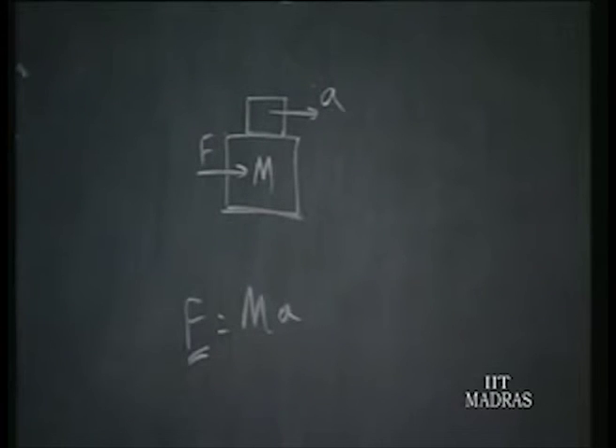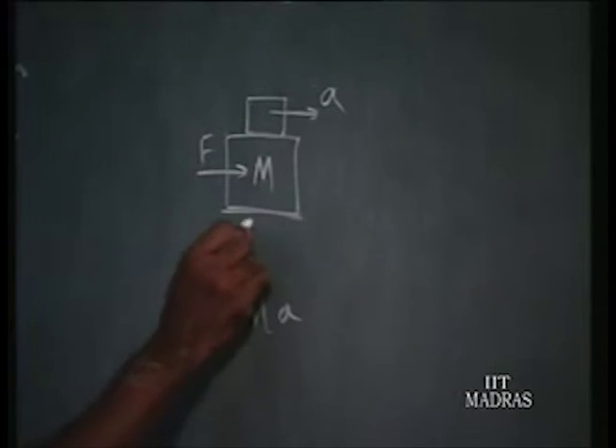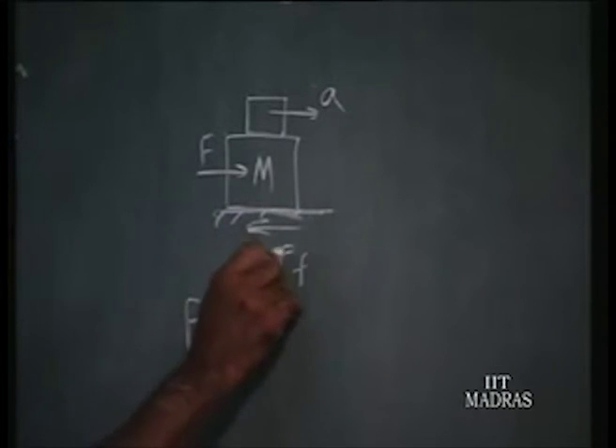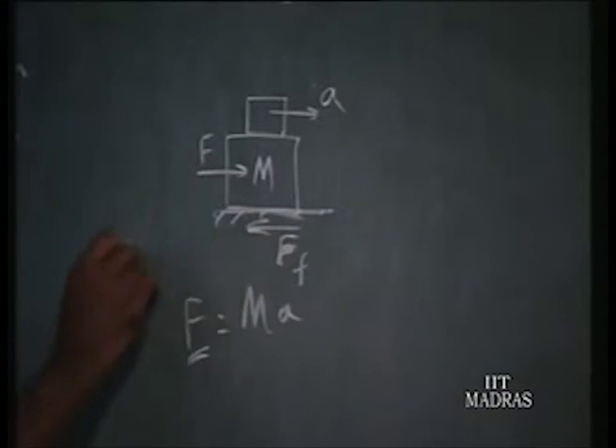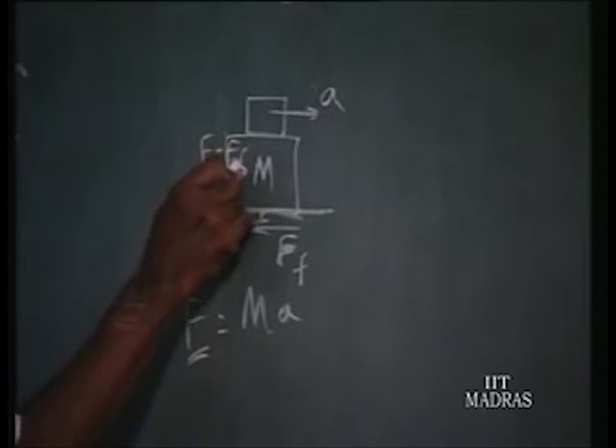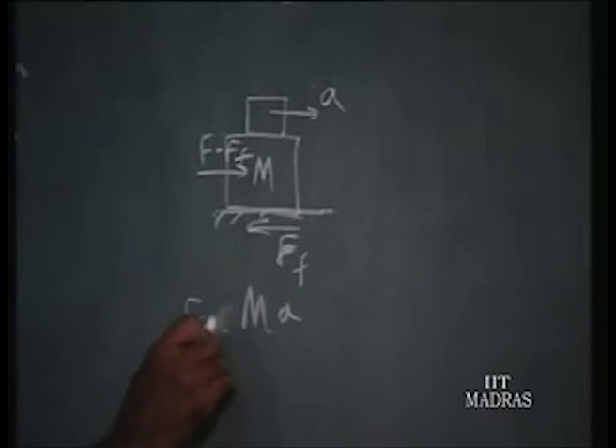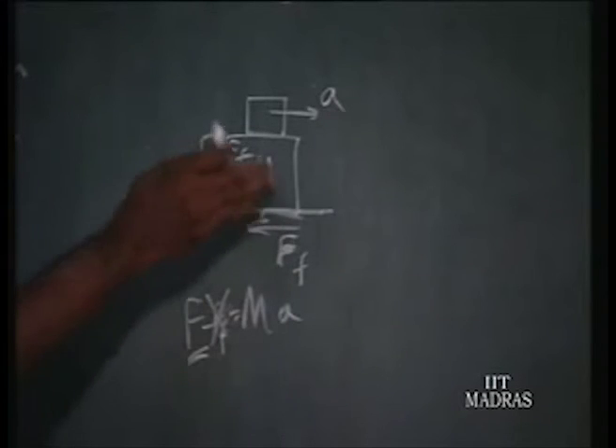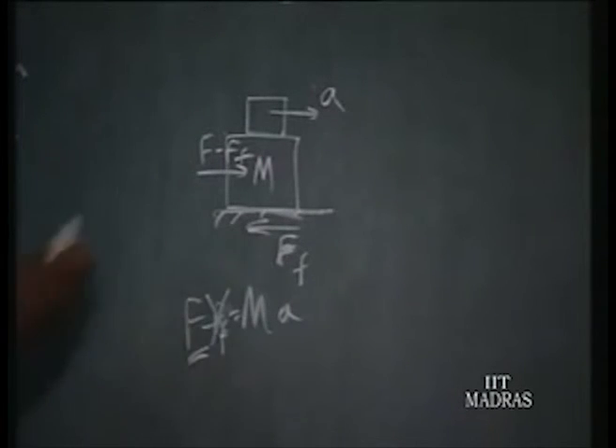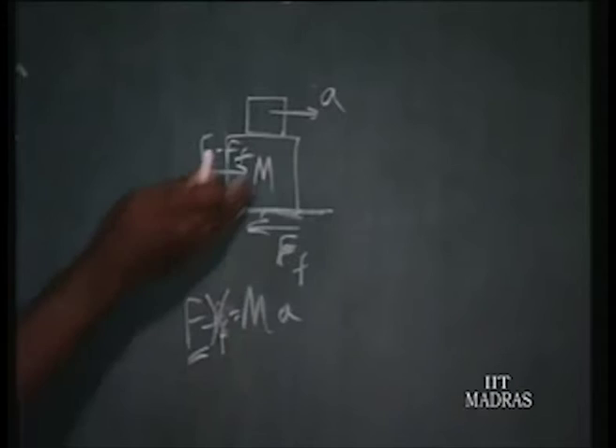But what is the drawback in this? It will measure only the resultant force. Suppose there is a friction force Ff as it is moving over a surface. The net force is F minus Ff, so F minus Ff will be equal to Ma. That means you should know the friction force. If you do not know the friction force, you will be assuming the net to be the force, so that will be an error. You are measuring a smaller force, but you will be calibrating it as a bigger force.